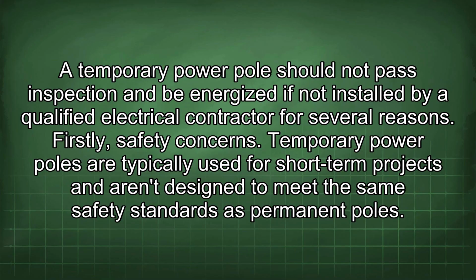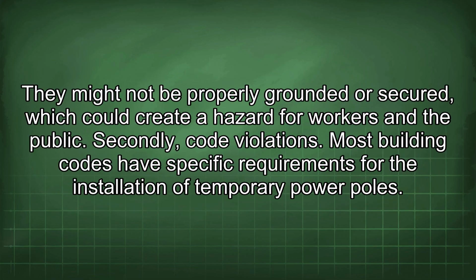A temporary power pole should not pass inspection and be energized if not installed by a qualified electrical contractor, for several reasons. Firstly, safety concerns. Temporary power poles are typically used for short-term projects and aren't designed to meet the same safety standards as permanent poles. They might not be properly grounded or secured, which could create a hazard for workers and the public.